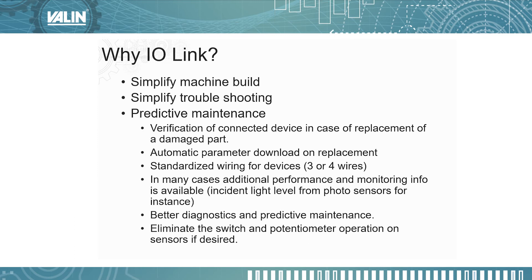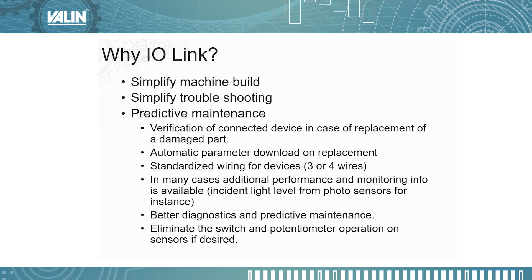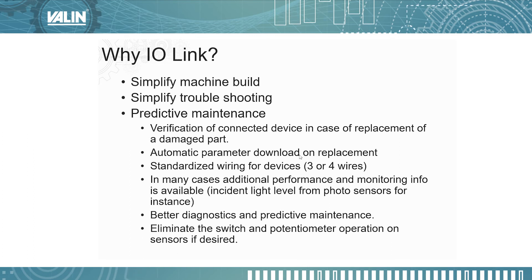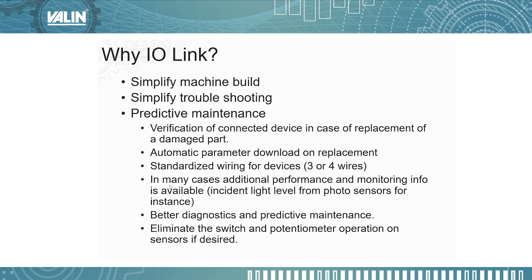In addition, there are multiple status bits that tell you whether the sensor is wired correctly, if it has a short circuit, or if it's the wrong sensor — for example, if you replaced a broken photo sensor with the wrong model, it'll tell you that. This is also good for predictive maintenance because you get verification of the connected device. In case of replacement, you can confirm you put the right part in, and automatic parameter download will configure it. The standardized wiring helps whether you have a three-wire or four-wire IO-Link device, and in many cases performance and monitoring info is available, like incident light level from photo sensors.